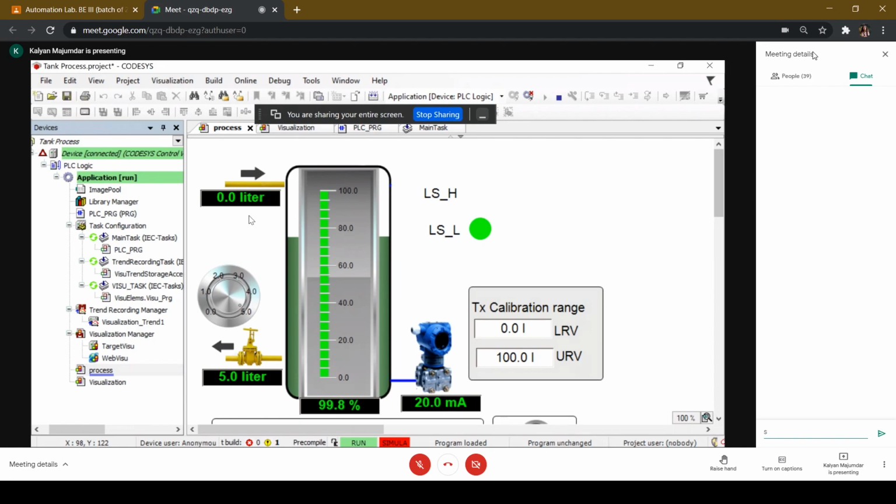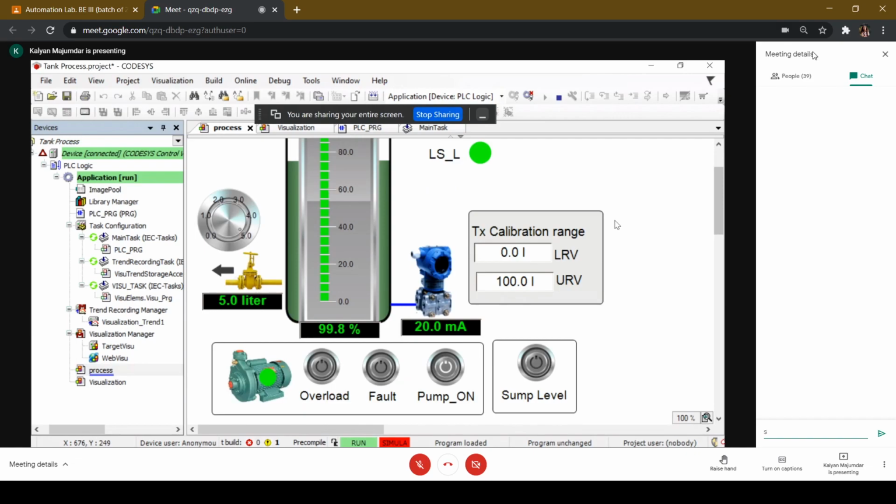It goes to 100, it stops, the integration stops, gets slightly below 100, আবার তোমার ইন্টিগ্রেশন শুরু করছে, gets to 100, it stops, and it keeps cycling around that high value of 100 on a continuous basis. তার জন্য মাঝে মধ্যে এটা 100 0 100 0 করে যাচ্ছে। সেটাই লেভেলেও দেখতে পাচ্ছ, there is a continuous fluctuation because of that. যে মুহূর্তে 100% এ যাচ্ছে, integration stops, level falls, আবার integration starts.